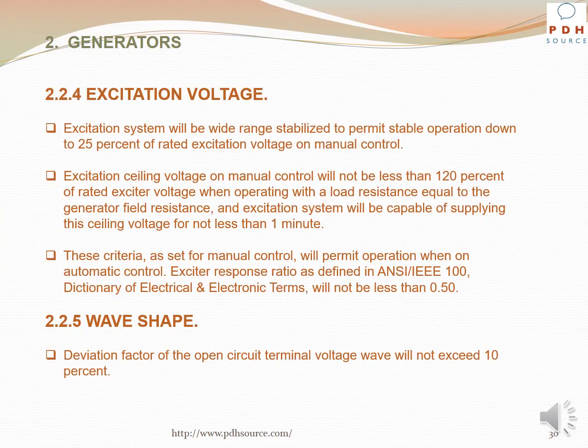Excitation system will be wide range stabilized to permit stable operation down to 25% of rated excitation voltage on manual control. Excitation ceiling voltage on manual control will not be less than 120% of rated exciter voltage when operating with a load resistance equal to the generator field resistance, and excitation system will be capable of supplying this ceiling voltage for not less than 1 minute. These criteria, as set forth for manual control, will permit operation when on automatic control.